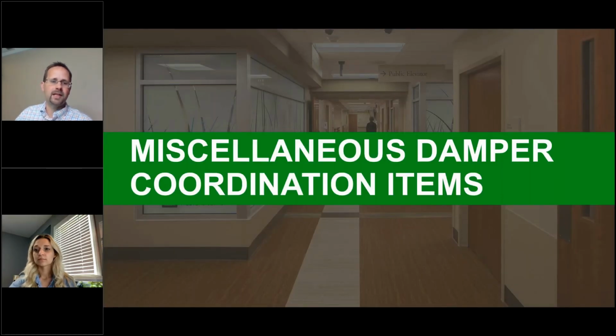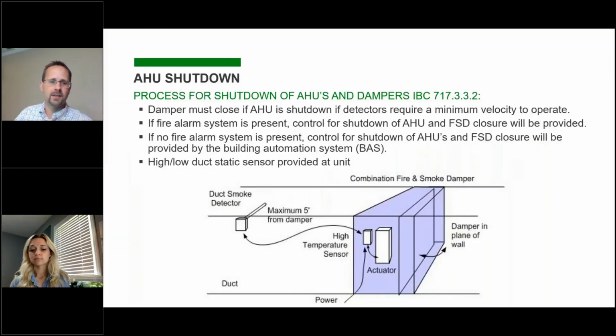So we're going to talk about coordination items, and really mostly regarding smoke dampers, because those require the most coordination and have the most options. First of all, the IBC requires that a smoke damper has to be shut down when an AHU is turned off if the smoke detectors require a certain velocity to work. On the next slide, we'll show a couple different smoke detectors, but there are certain smoke detectors, the probe type, that if you have no velocity across them, they're not going to be able to detect smoke. And there are others, more spot type, that can work with no velocity.